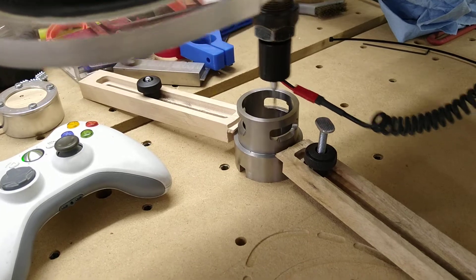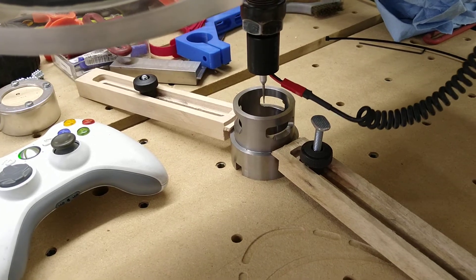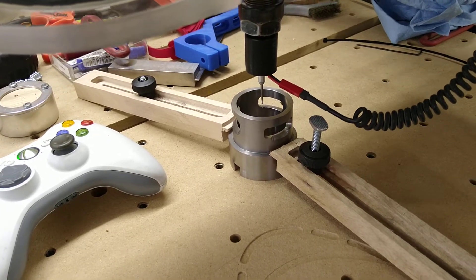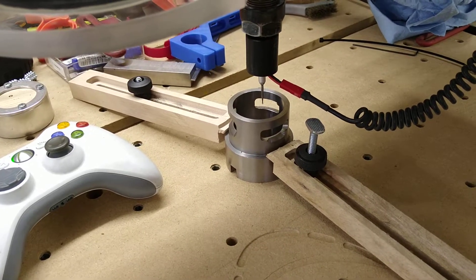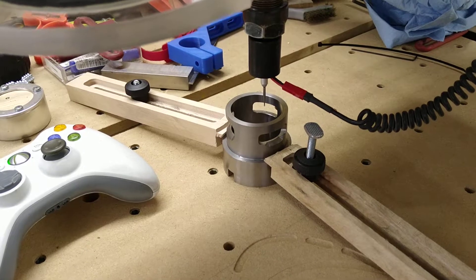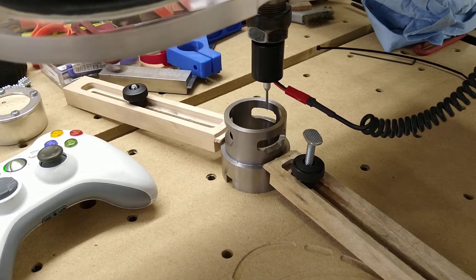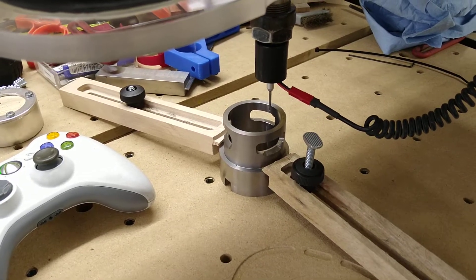First thing it does is finds the center of the ring gauge and it'll start a calibration routine and pick up every 10 degrees of angle.